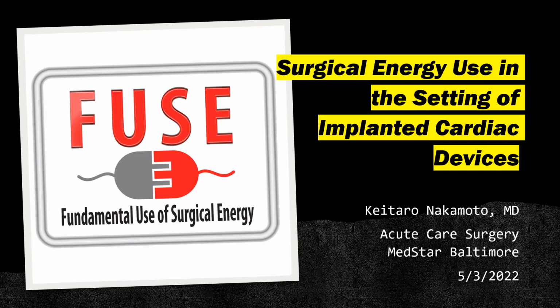The difference between 3 and 5 is the distance it vibrates. On 5, it vibrates 100 microns; on 3, it vibrates 70 microns. Think of a saw moving a longer distance at the same speed, it cuts through wood quicker. So 5 at 100 microns excursion goes through tissue much quicker, but gets poorer hemostasis. It's a vibration.